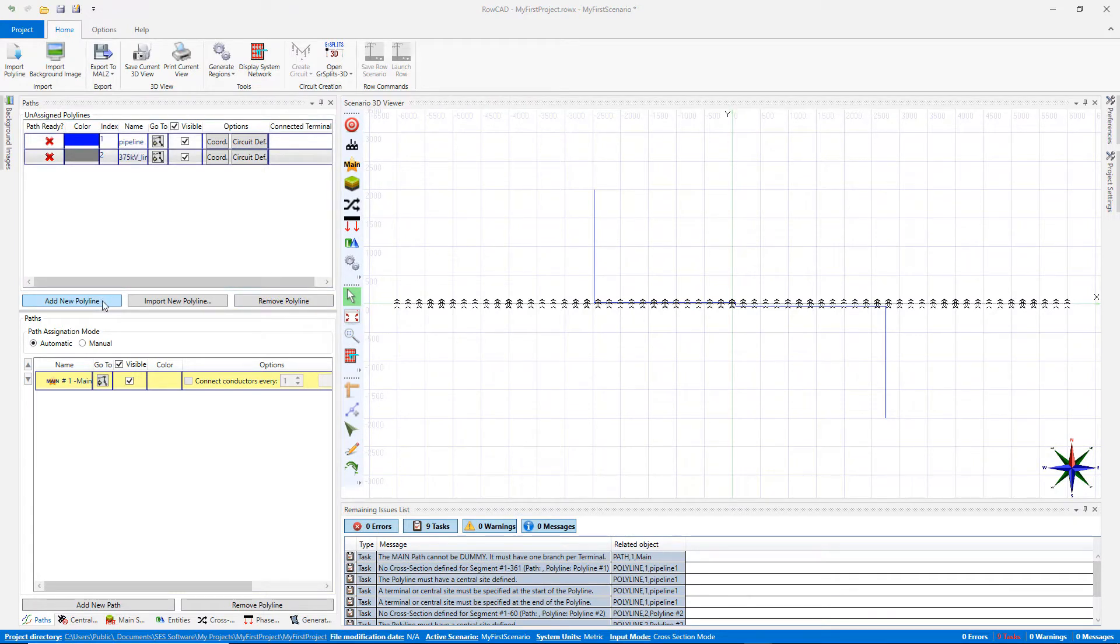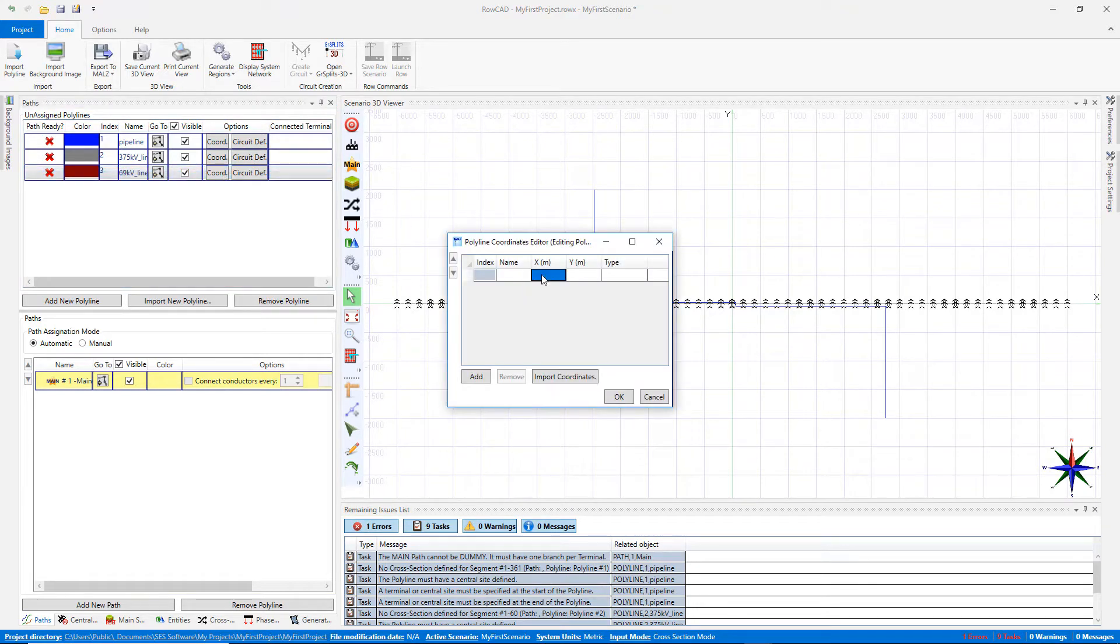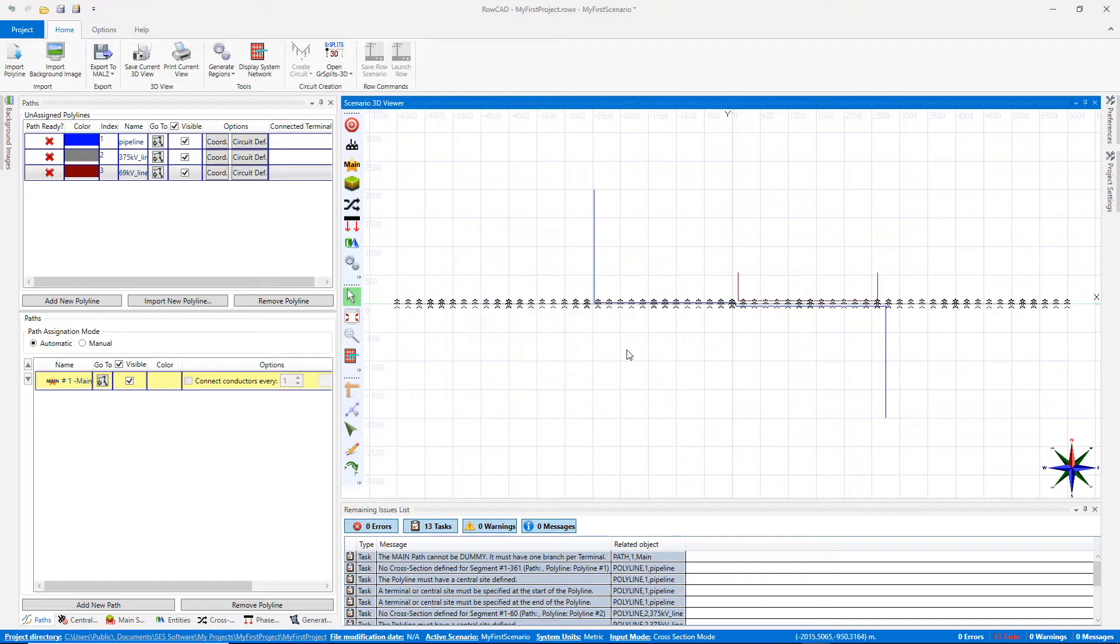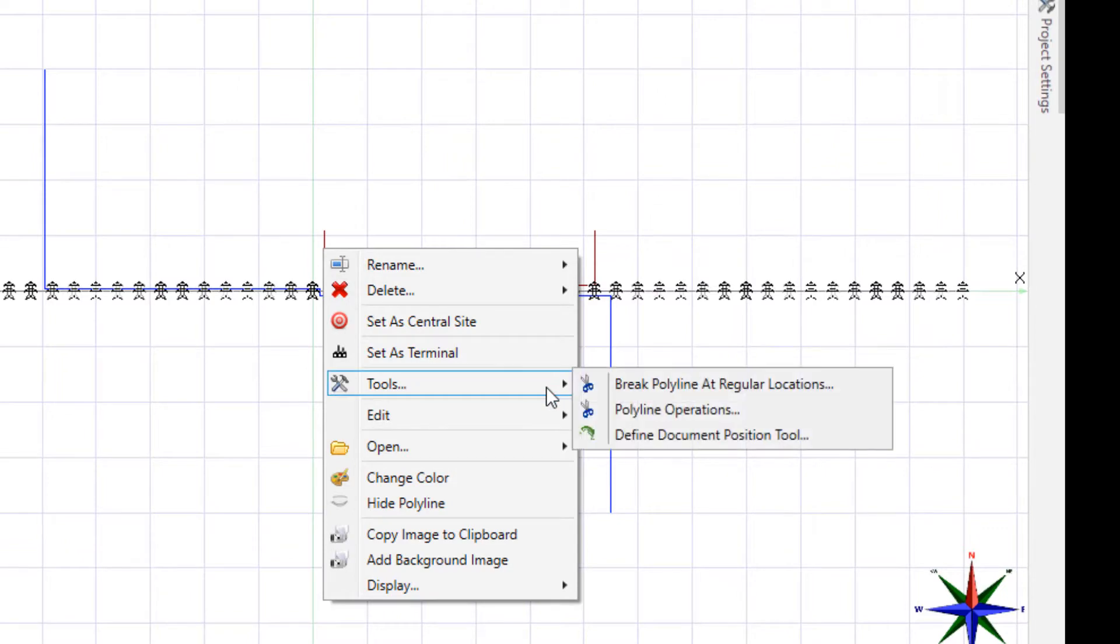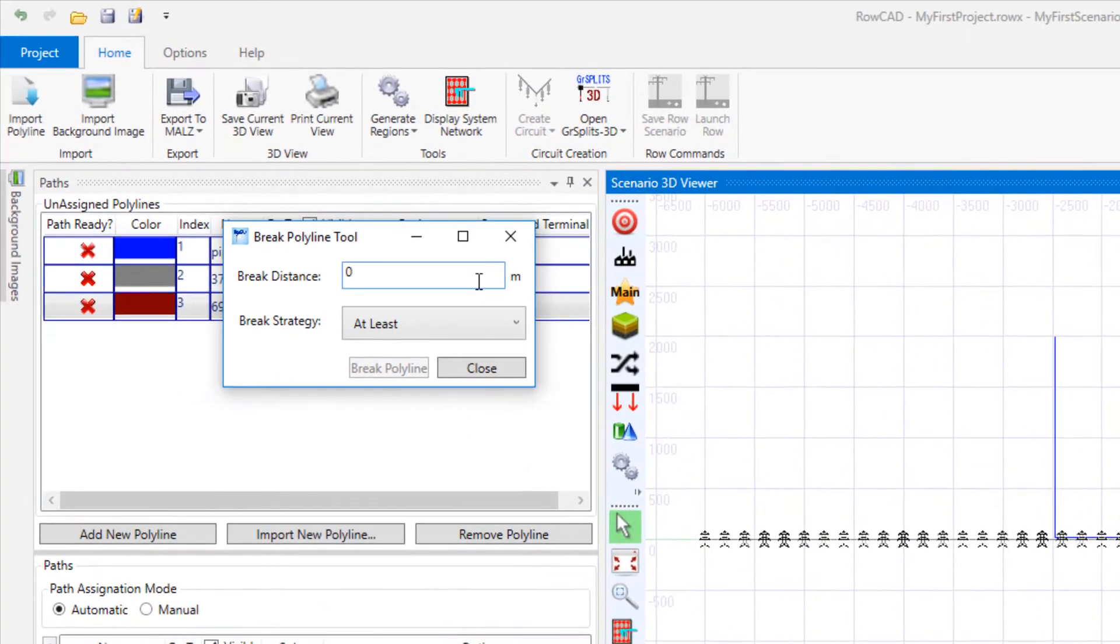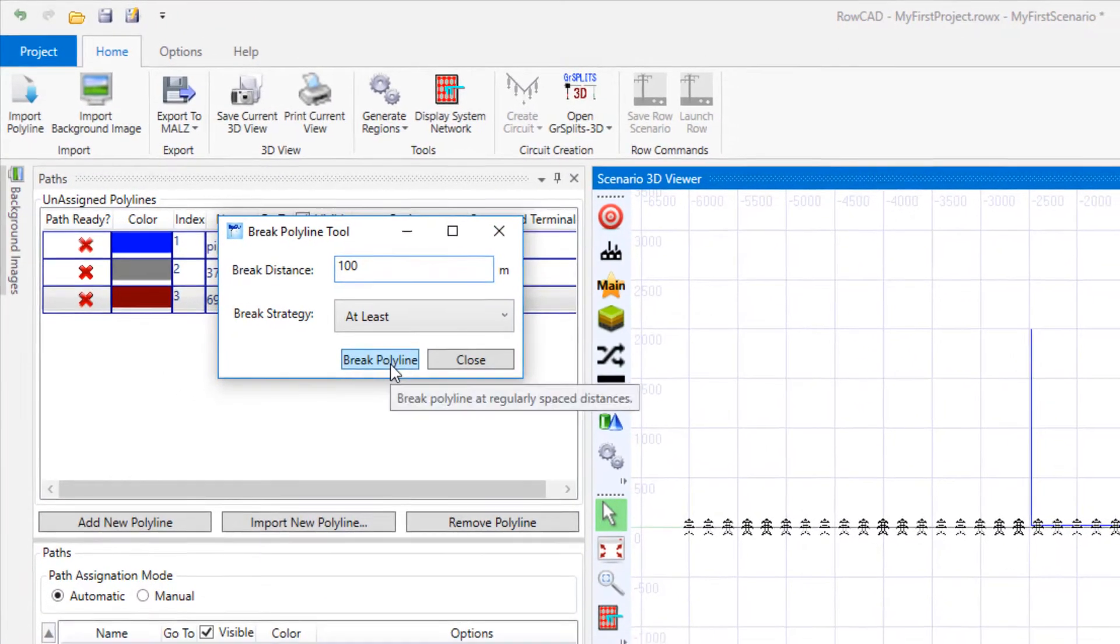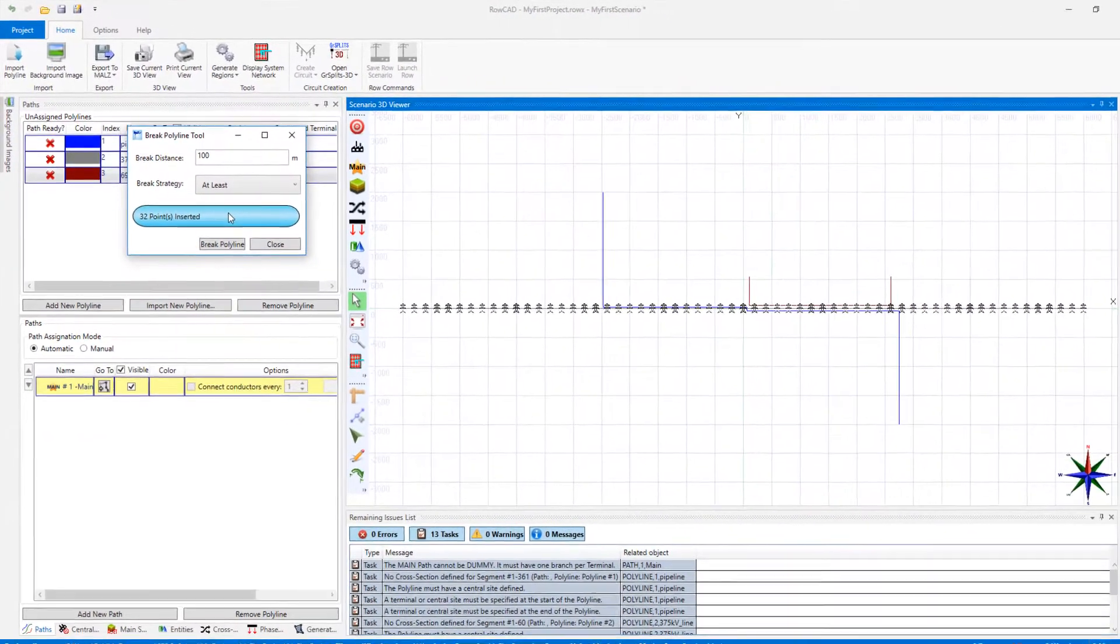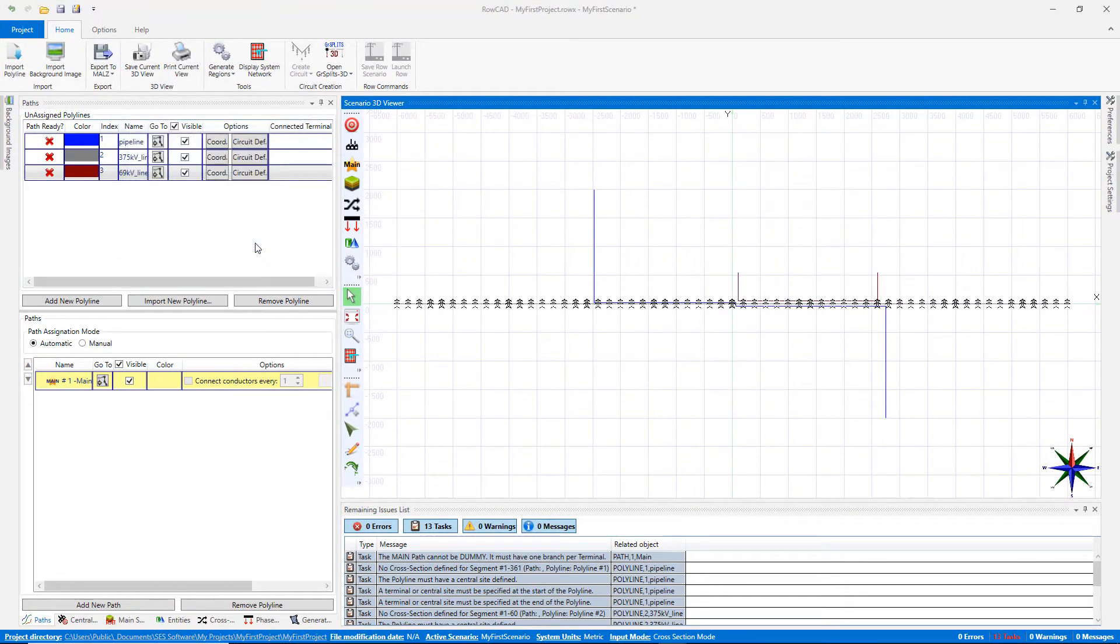For the 69 kV line, we enter the coordinates manually. This transmission line has an average span length of 100 meters. In order to break the polyline, right-click on the polyline, then from Tools menu, choose Break Polyline at regular locations. From this window, choose the break distance and click on Break Polyline button. You will see new nodes are added to the polyline coordinate window.